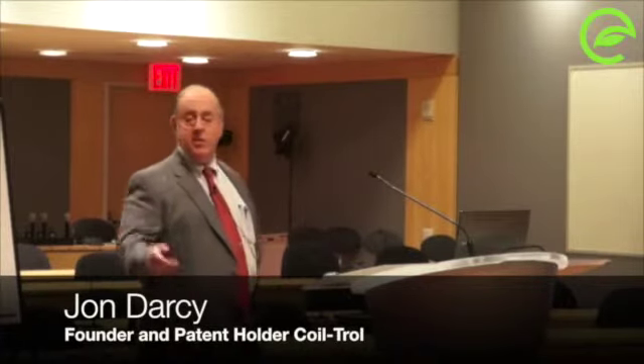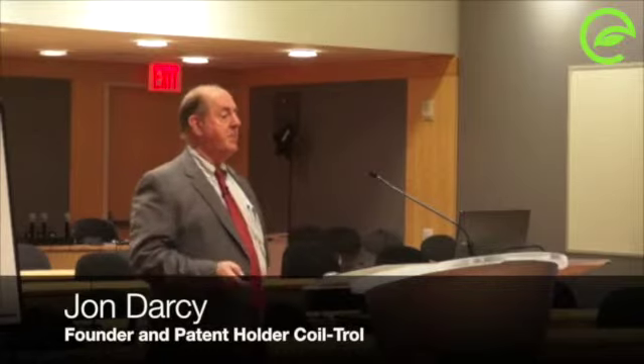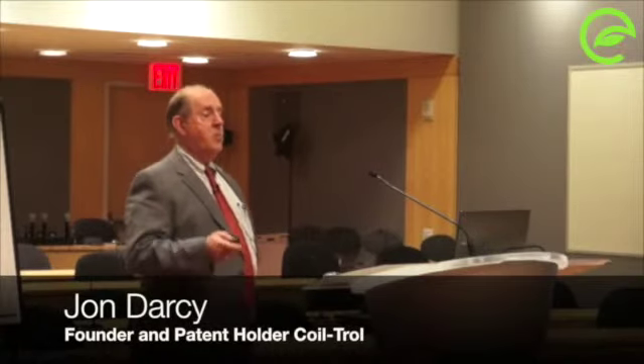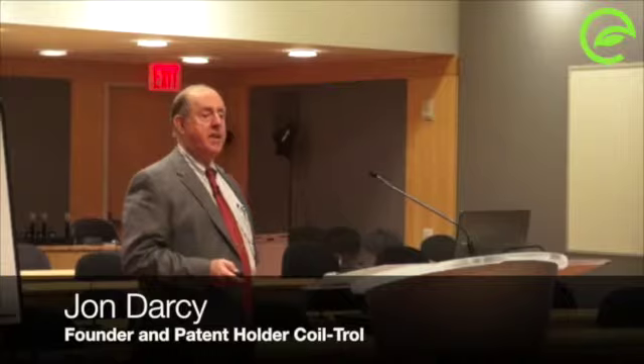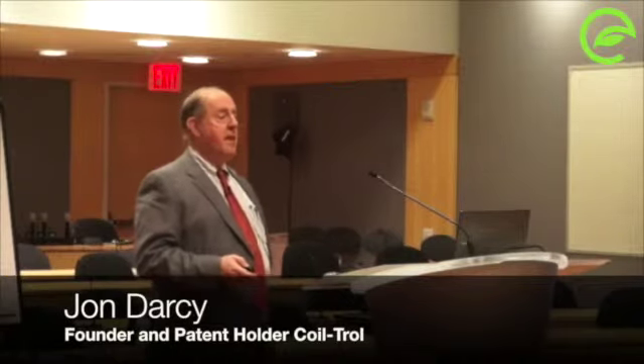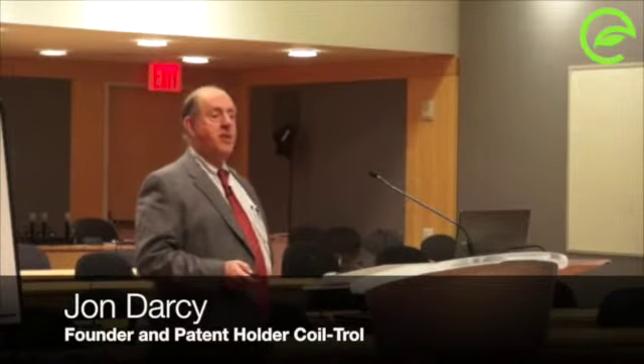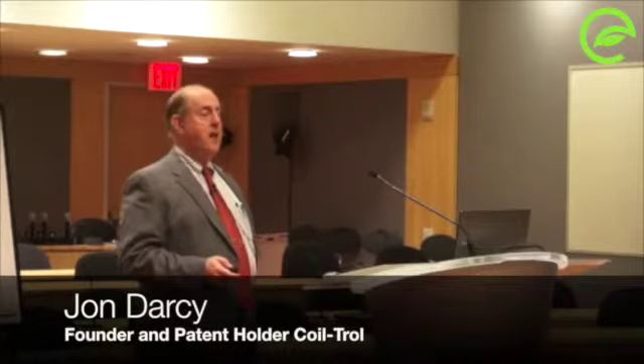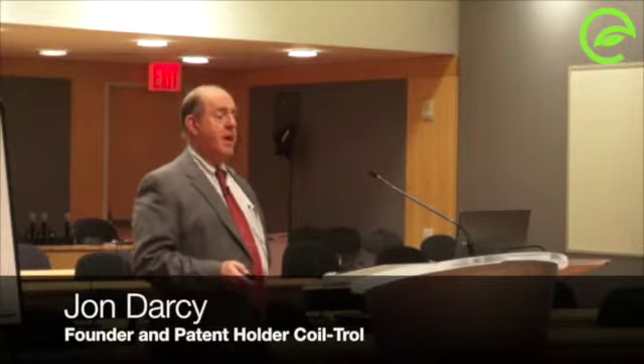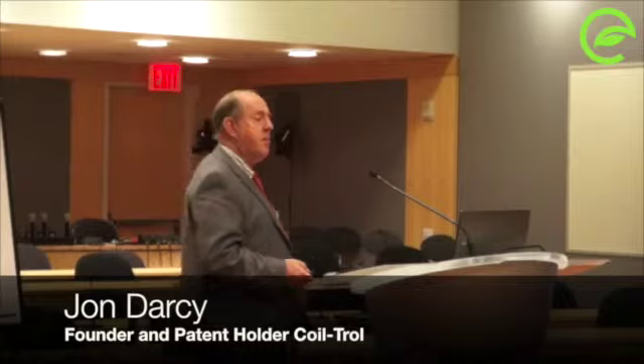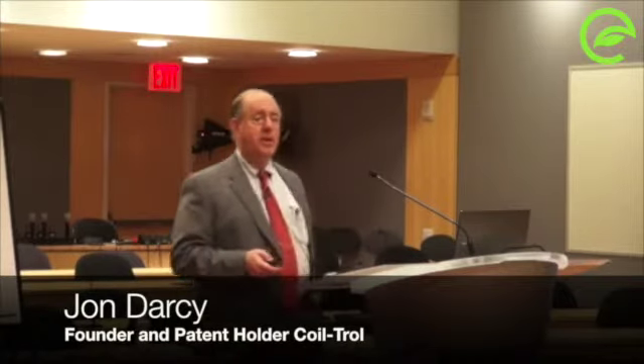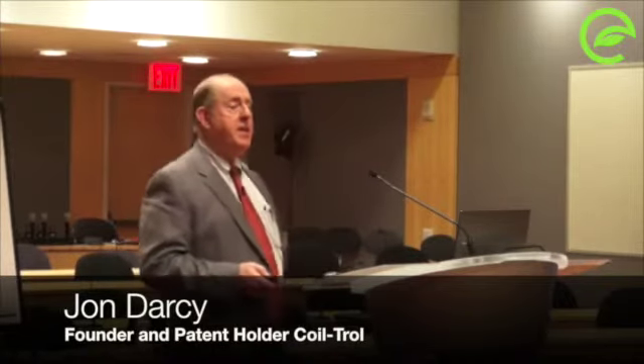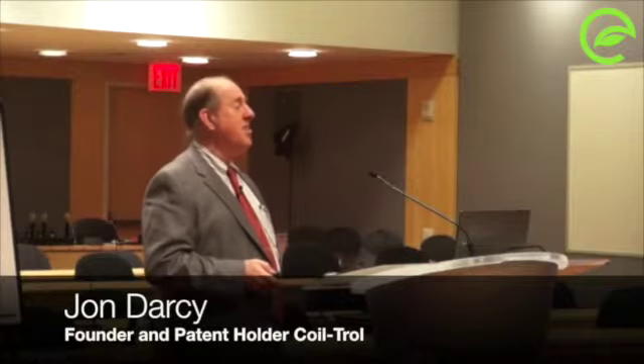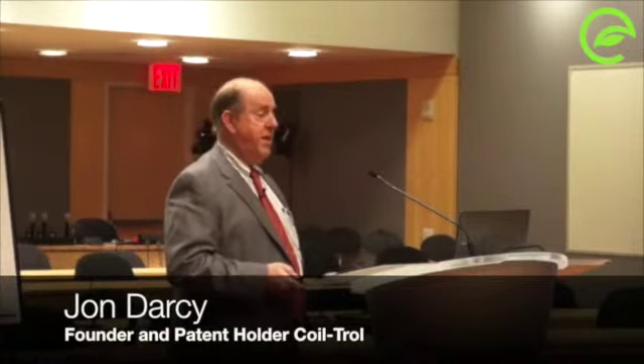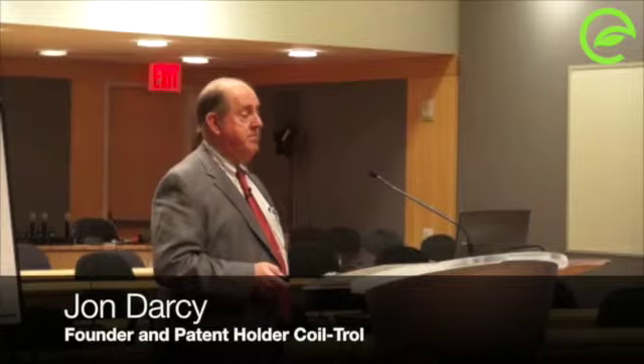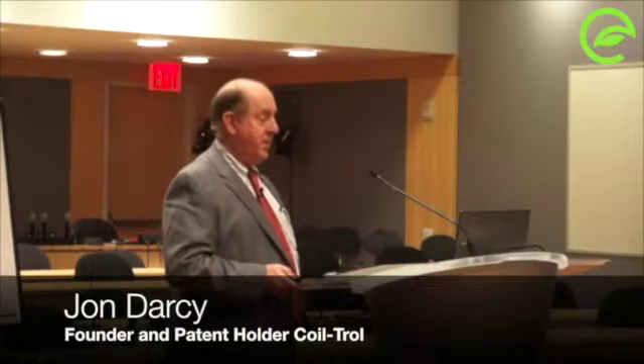We got rid of all of the CRTs and we put in nice LED monitors, okay? Everybody used to have a printer on their desk that stayed cycled on all the time. Now you have a central printing station where if it isn't used in 5 minutes, it cycles itself down, okay? All the sources of sensible heat have disappeared inside the building. When we finally put LEDs in the building, the problem is even going to get worse, okay? You're going to have to put reheats in because there's no other way to get around it.